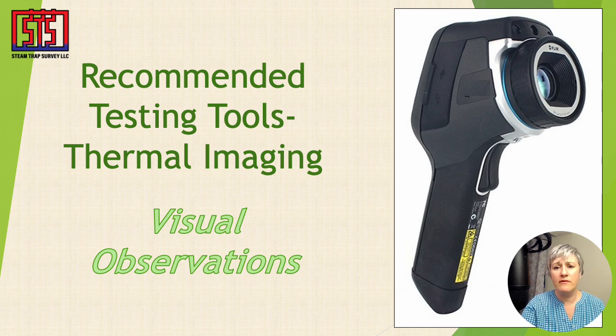Visual observations. Although limited in its scope, visual observation is an important first step in determining whether a steam trap is operating as designed. For example, certain visual signs, such as a lack of any condensate discharge or extremely large quantities of steam leaking out of a trap, may indicate the need for trap repair. This type of visual is limited to open condensate return systems dumping to the ground. Traps can also be externally inspected for pinhole, connection point, or gasket leaks.